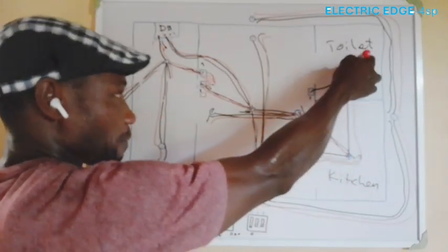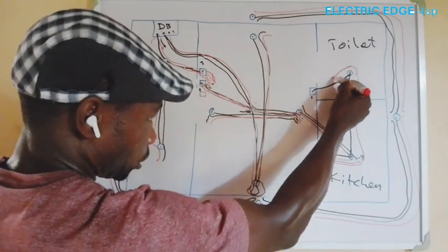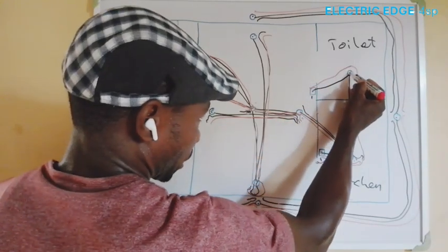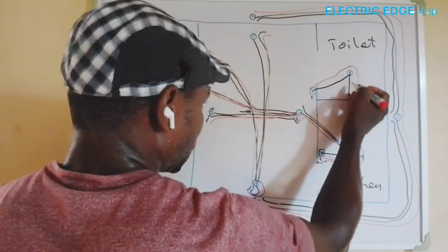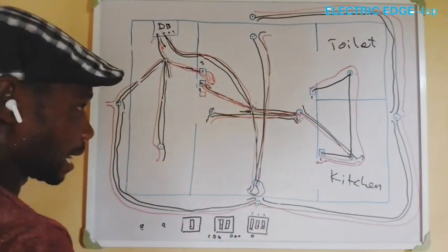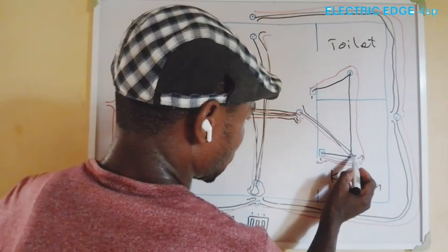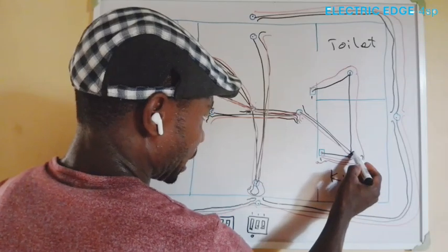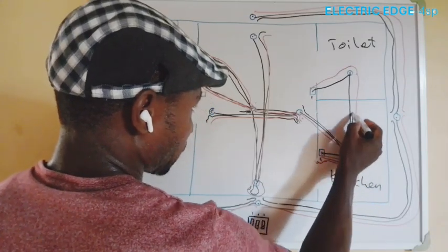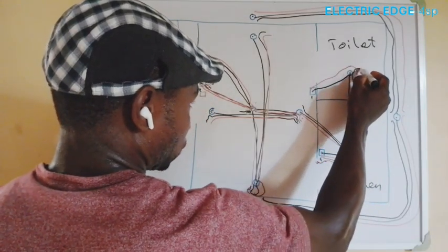From here, remember our mains travel from switch to switch. It will go to this switch. It will not stop here. So this red is going inside the pipe with a black, and this black is going to start from here. It will not start from the switch. A black will join it from here inside the conduit pipe. To this point, it will stop.